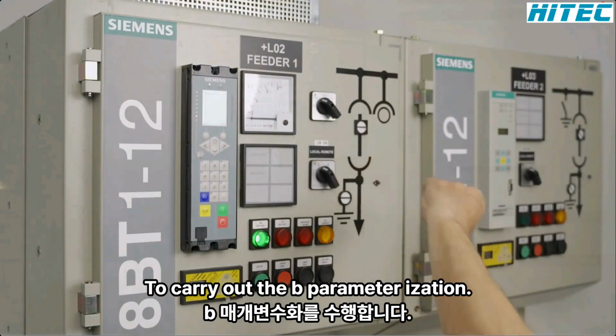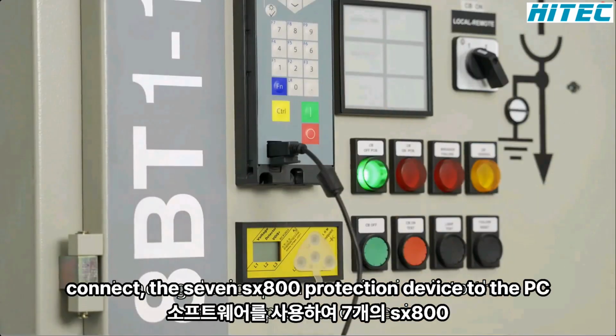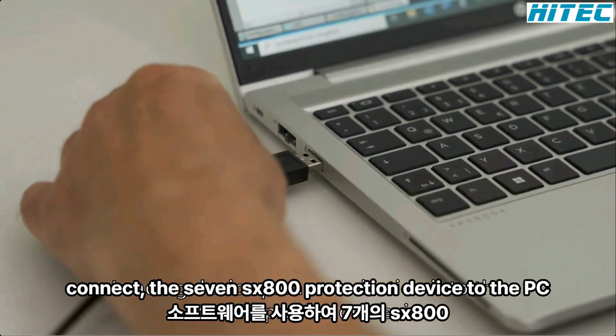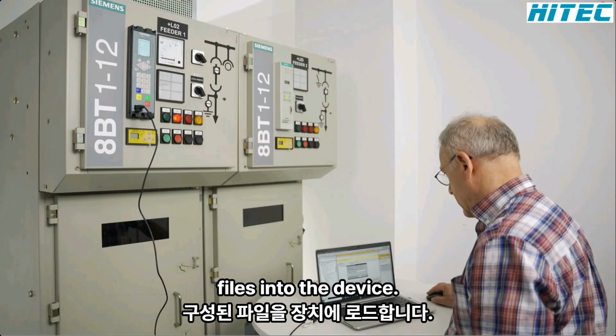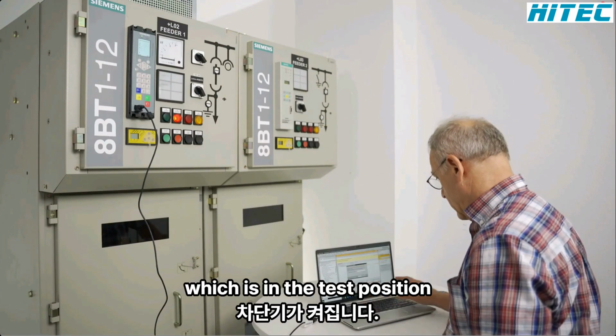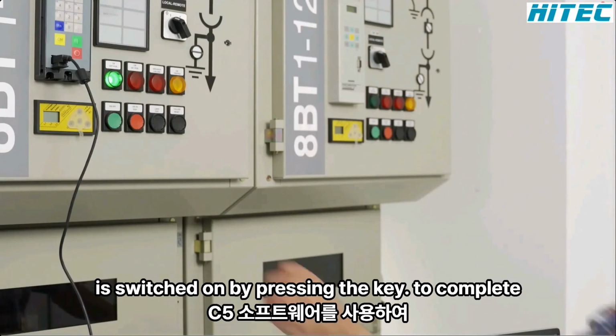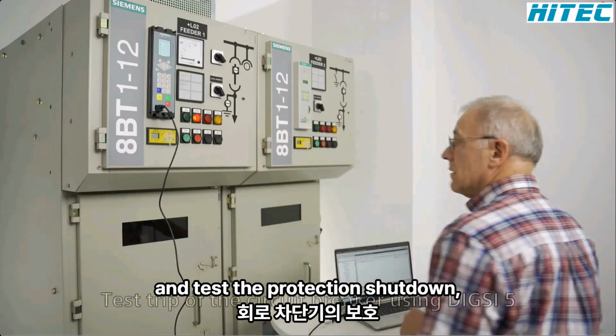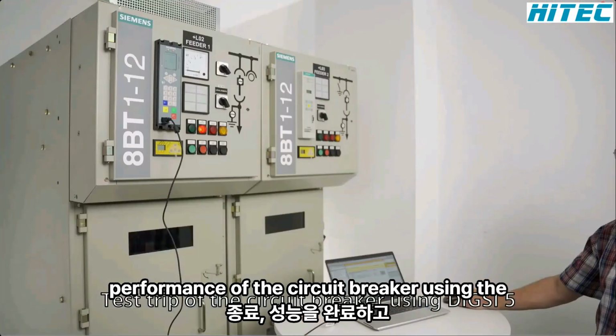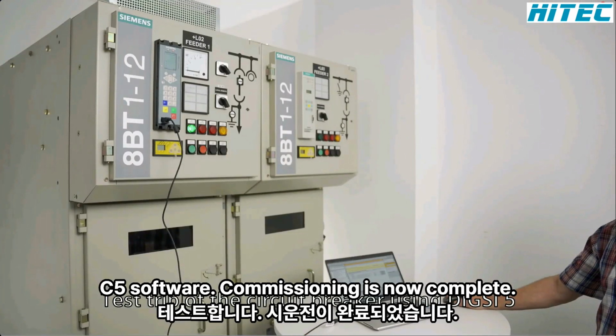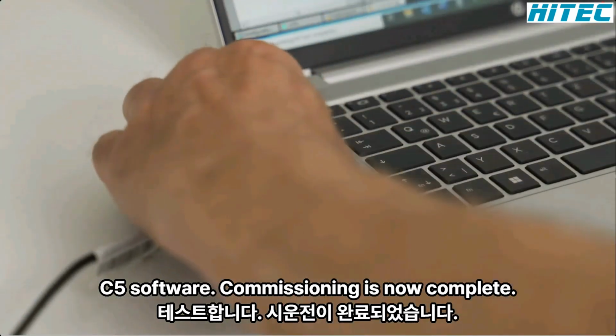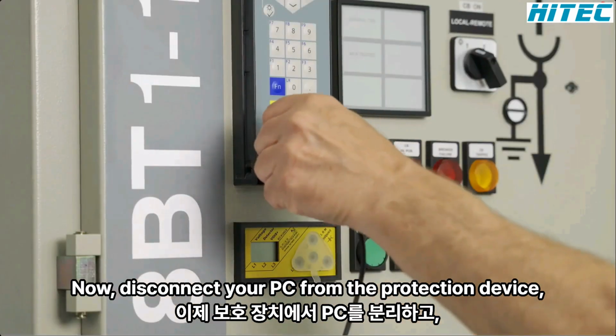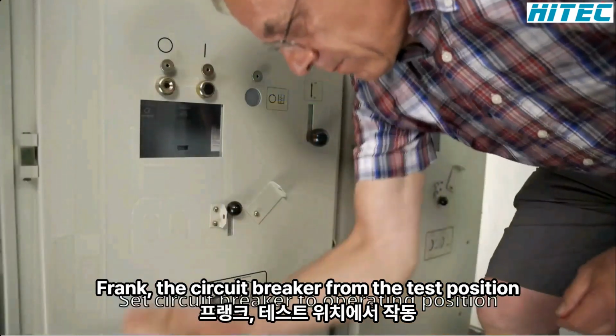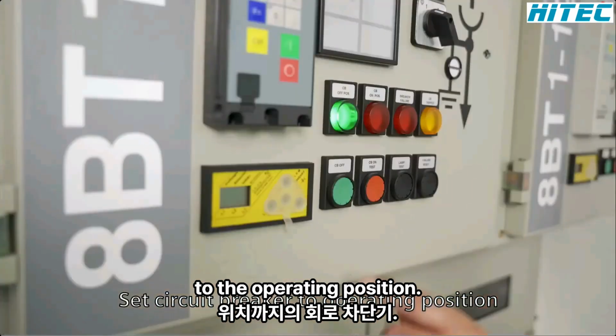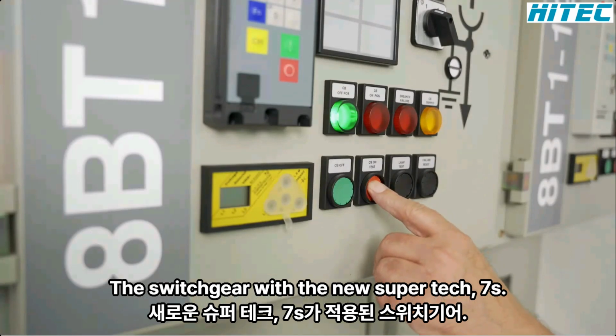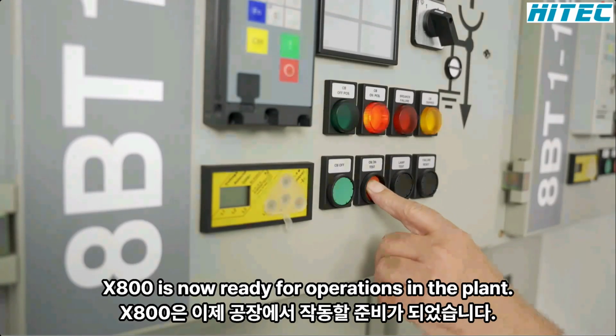To carry out device parameterization with the DIGSI 5 engineering software, connect the 7SX800 protection device to the PC and load the configured files into the device. The circuit breaker, which is in the test position, is switched on by pressing the key. To complete and test the protection shutdown, perform a trip of the circuit breaker using the DIGSI 5 software. Commissioning is now complete. Now disconnect your PC from the protection device. Crank the circuit breaker from the test position to the operating position. The switchgear with the new SIPROTEC 7SX800 is now ready for operation in the plant.